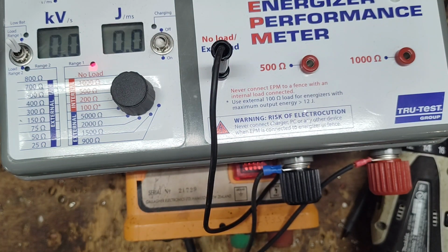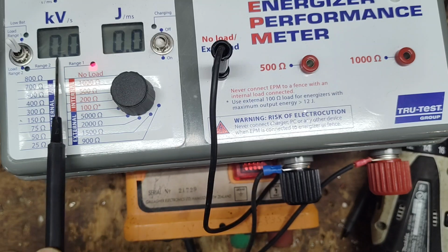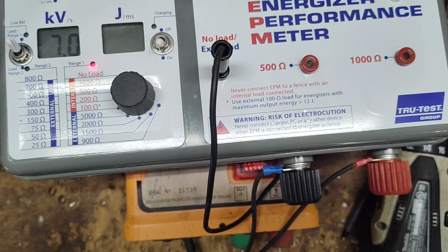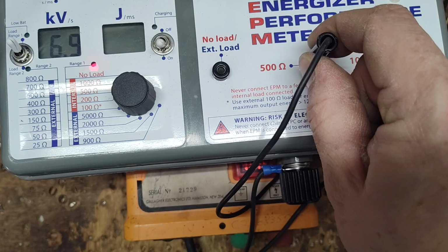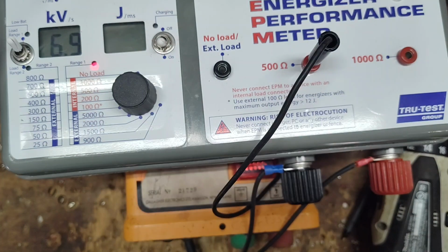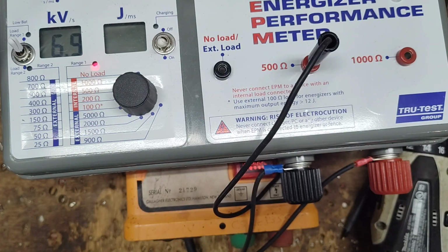Clicking and flashing along there. Watch this number right there. It's our peak voltage, and right around 7 kV, right where it's supposed to be. Now we'll put a 500 ohm load on it, which is pretty standard, and we'll see what kind of voltage it drops down to. 4.2 at 1.4 joule output. So it's almost double the power out of it compared to what it was from the factory way back when.